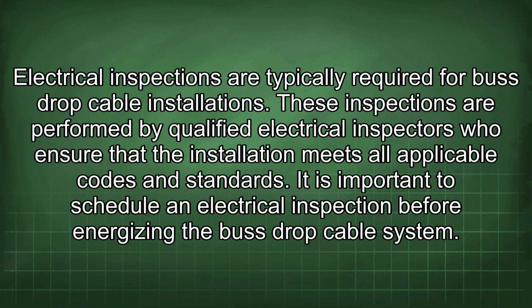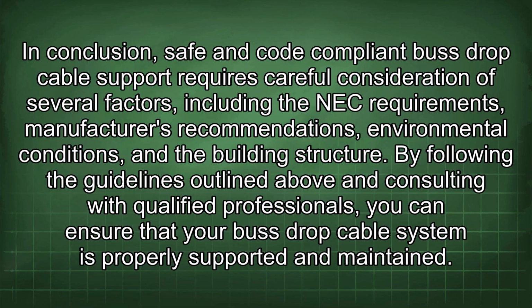Electrical inspections are typically required for bus drop cable installations. These inspections are performed by qualified electrical inspectors who ensure that the installation meets all applicable codes and standards. It is important to schedule an electrical inspection before energizing the bus drop cable system. In conclusion, safe and code-compliant bus drop cable support requires careful consideration of several factors, including the NEC requirements, manufacturers' recommendations, environmental conditions, and the building structure. By following the guidelines outlined above and consulting with qualified professionals, you can ensure that your bus drop cable system is properly supported and maintained.